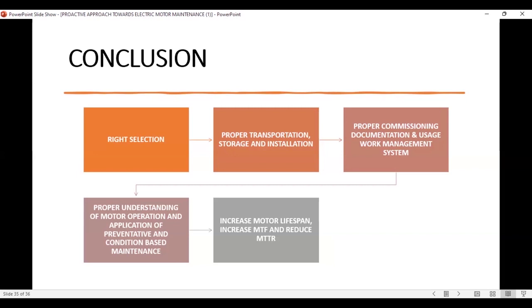Conclusively, I would say that motor maintenance starts with right selection. You know you are going to mount your motor vertically, and you buy a general purpose motor without a shaft slinger. Chances are that the bearing will fail prematurely. Right selection: you know you are going to run your crusher, and you go and buy a NEMA B design instead of a NEMA C design. The motor will trip frequently, and chances are that you lose your starters, you lose your breakers, you lose your insulation. Right selection is very important.